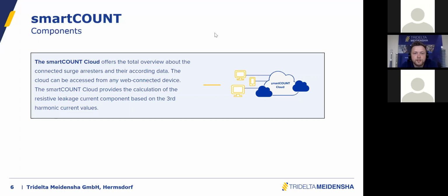And you will also see the related surge arrestor data you have configured before. So which surge arrestor is it, on which transformer is it located, in which substation is it located, just as you configured. And you will also see the related leakage current data to this surge arrestor, and you will see the related discharge currents for the certain surge arrestor. If you don't like the online solution, we also have an offline solution where you can download all the raw data to Excel from your smartphone. Very easy.